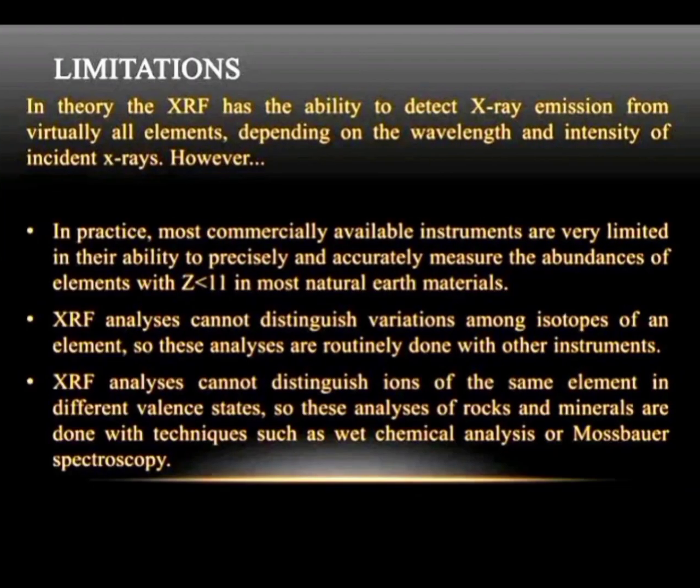Limitation. In theory, XRF has the ability to detect X-ray emission from virtually all elements depending on the wavelength and intensity of incident X-rays. However, in practice, most commercially available instruments are very limited in their ability to precisely and accurately measure the abundance of the elements with Z less than 11 in most natural earth materials.